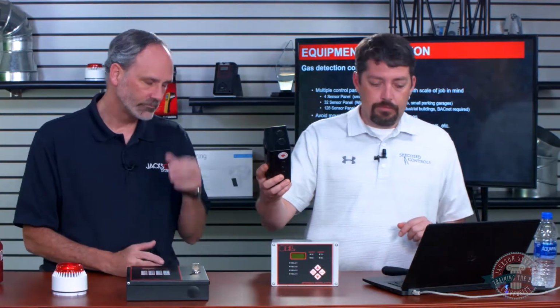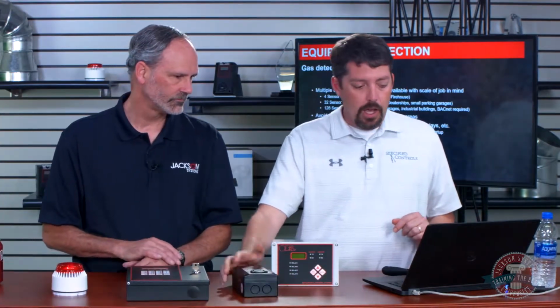Let's find the answer. The sensor we're looking at right here, which is capable of about 40-something different gases, has a temperature range of -40 to 70 degrees. Excuse me, I'm sorry, that's Celsius. -40 to 158 degrees Fahrenheit, depending on the sensor itself. So, to give you the answer on NH3, which is essentially ammonia, it is -40 to 158. So we can do that. Yep, you could mount that right in the freezer if you chose to. There you go. Yes, sir.